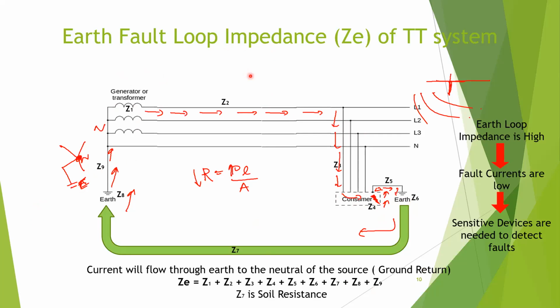Because the electrode resistance and the earth resistance are higher, our fault currents are low. So the earth loop impedance is high because there is a ground return. Ground return is the non-metallic path, and it has a much higher resistance than the metallic path. So this ZE will be higher compared to the other earthing systems, which we will come to later. So ZE will be somewhat higher, so our fault current will be lower.